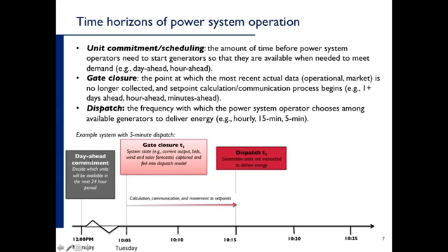Over here on the left, you see the gray box, the day-ahead unit commitment. The timeline shows that at 12 p.m.—again, that's not a requirement, but many power systems will do the day-ahead commitment by noon the day before the period in question—we tie down which units we're going to have available.